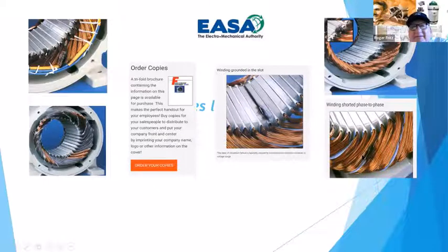And that's another thing a person should look at when you're designing the systems: what motor am I buying? Because you can buy a 1200 RPM motor, 50 horsepower, and it'll have a lot more torque than a 50 horsepower 1800 RPM. And you can put gearing in, but then to gear it back down to 1200 RPM, you have losses in the gearing. So the ideal thing is actually to put in a high multi-pole winding. They're bigger, a little bit more costly, but the longevity of that motor can be a great deal higher than what it is today.